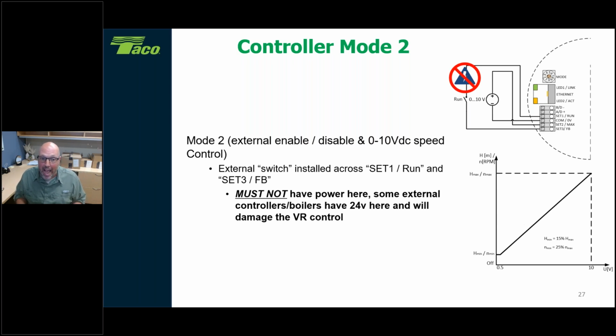Now what we have to remember on this end switch coming in is that there is no power here, absolutely 0 power. There are some boiler manufacturers out there that operate in this mode. They do have a switch and a 0 to 10 coming out of it. And if you put power across that terminal, across set 1 and set 3 with that switch, we are going to let the magic smoke out of the circulator, and that circuit board gets fried, and we have to replace just the circuit board, which is nice. You don't have to change out the whole pump, but we do have a circuit board that needs to be changed out.